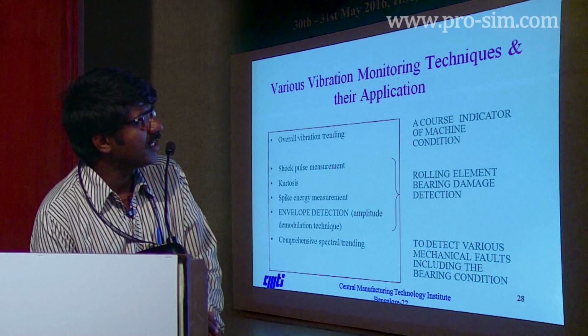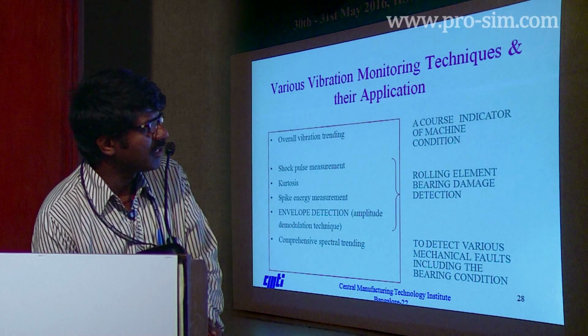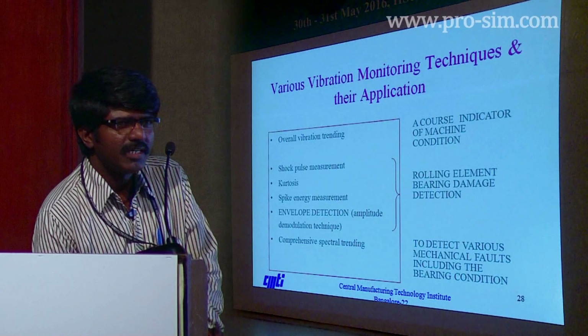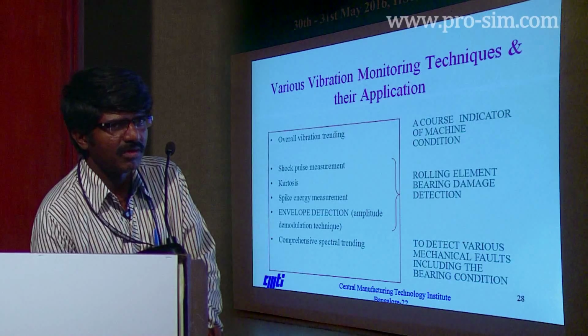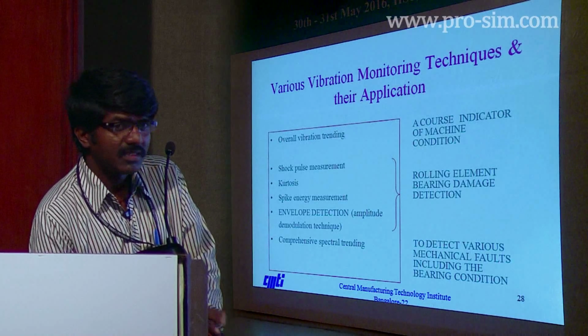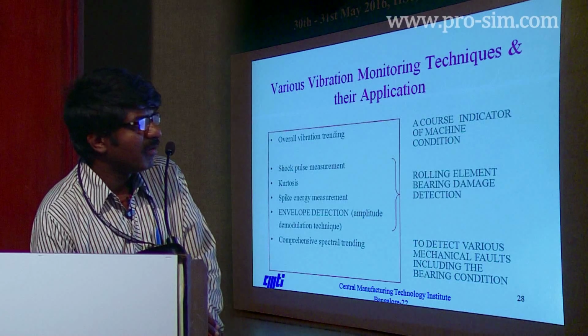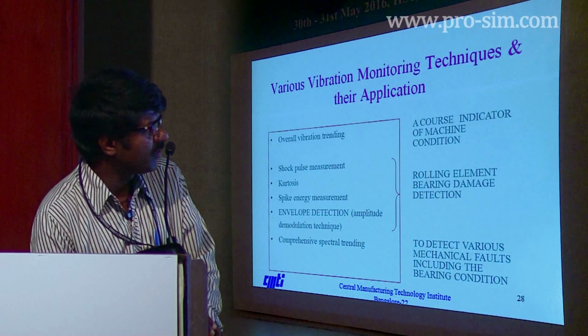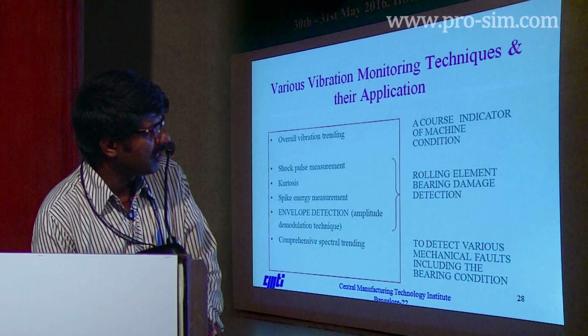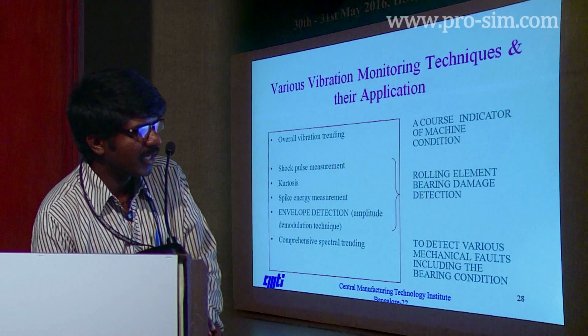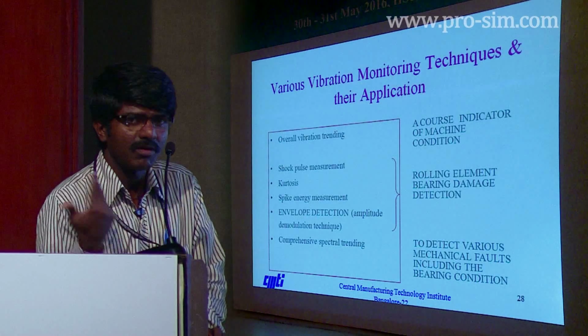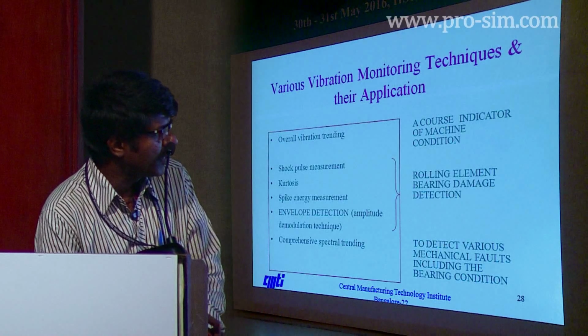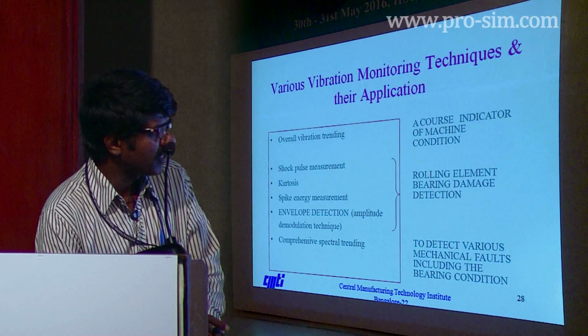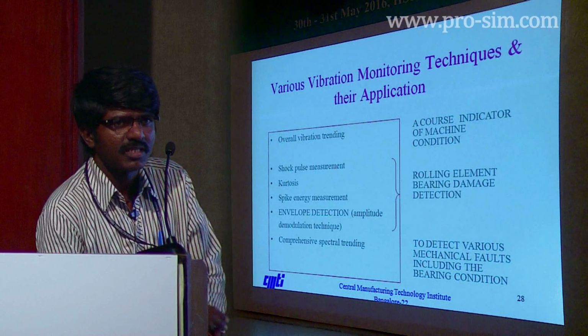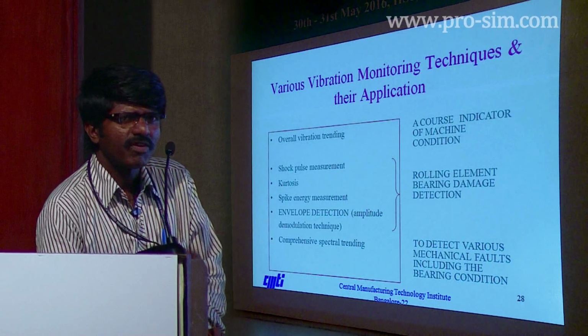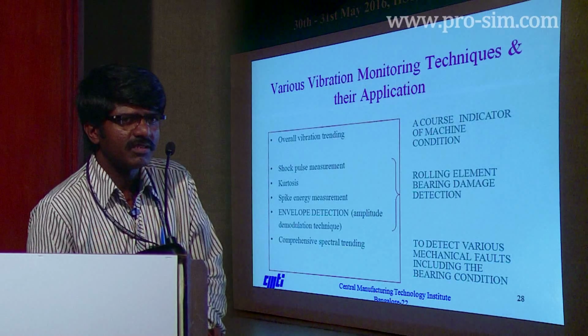Now, various monitoring techniques and their application we will discuss. Overall vibration trending: you can use overall vibration trending also. It is a coarse indicator of the machine condition. It is not going to give you a 100% health condition of the machines. It has drawbacks that we will discuss in the coming slides. For bearing damage or bearing faults, we can use shock pulse, kurtosis, spike energy. Earlier people were using this. Nowadays we are not using this. We are going for envelope detection, also called the amplitude demodulation technique. And then comprehensive spectral trending. We go for comprehensive spectral trending because you can detect the various faults we have discussed in the initial slides. We can find all the faults in the comprehensive spectral evaluation or spectral analysis.